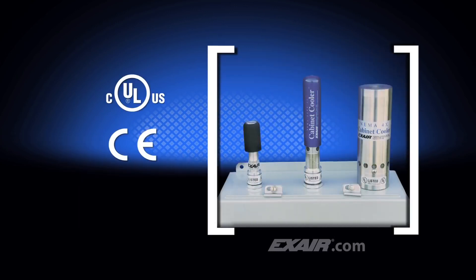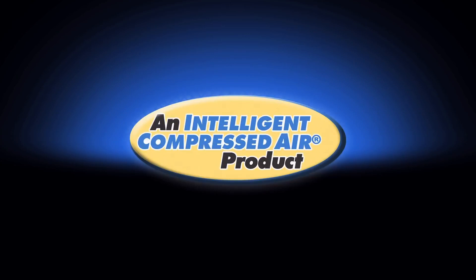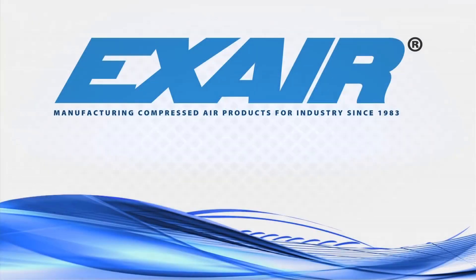EXAIR manufactures a complete line of cabinet coolers that are in stock and ready for use for your application. If the hot summer weather is creating the problem, in most cases 2,000 BTUs per hour is enough refrigeration to offset the summertime heat load, regardless of the panel size.